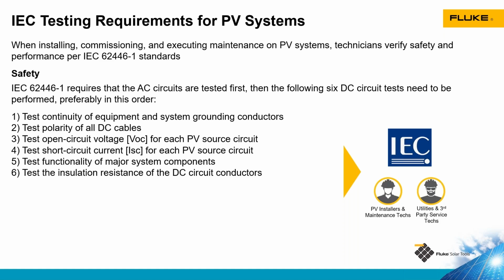We'll make sure that our major components are functioning properly, so the disconnects work right, the circuit breakers are working, the inverter is operating properly. And finally, in this category, we'll do an insulation resistance test to ensure the conductors have not been compromised. The second class of tests are performance tests, and in this case, it's IV curve tracing, making sure that our modules and strings of modules are operating as we expect. This standard also requires all of these tests to be documented, along with some other document requirements that will be transferred to the owner of the system.